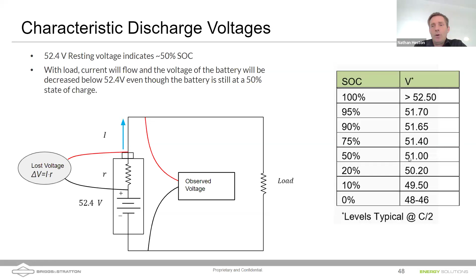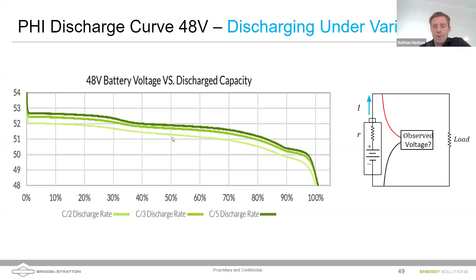This is actually somewhat dependent on temperature. I'm showing different load rates here, and as I load the battery and discharge it more quickly, you can see those voltage curves shift downward. To get even more sophisticated, if I get the batteries really cold and load them at C/2, it really shifts down.